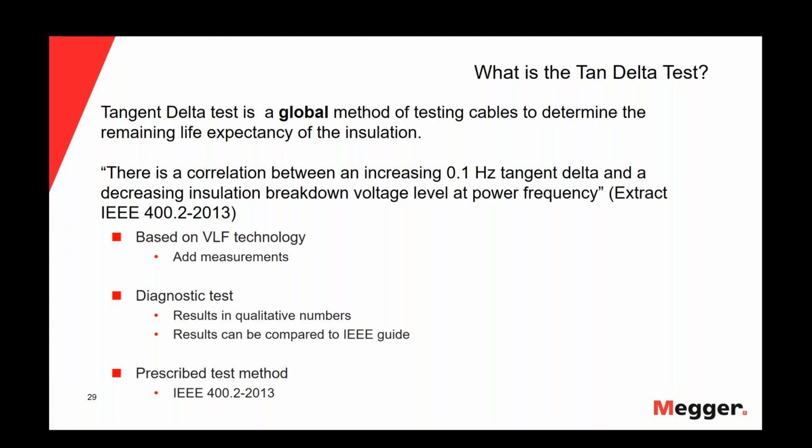Indeed, this is an extract of the IEEE 400.2, and the Tan Delta test is based on VLF technology. Of course, it's a diagnostic test, and it's a prescribed test method by the IEEE 400.2.